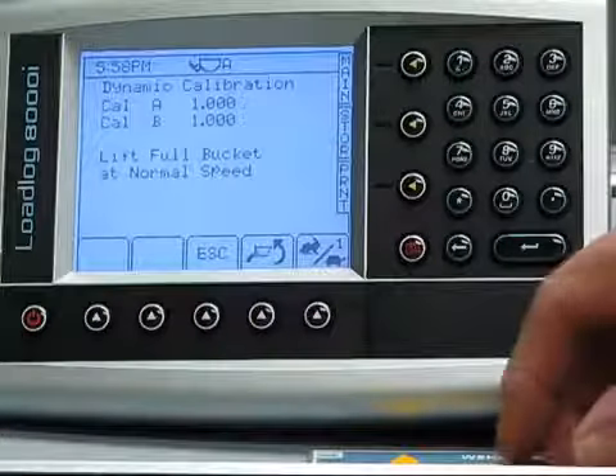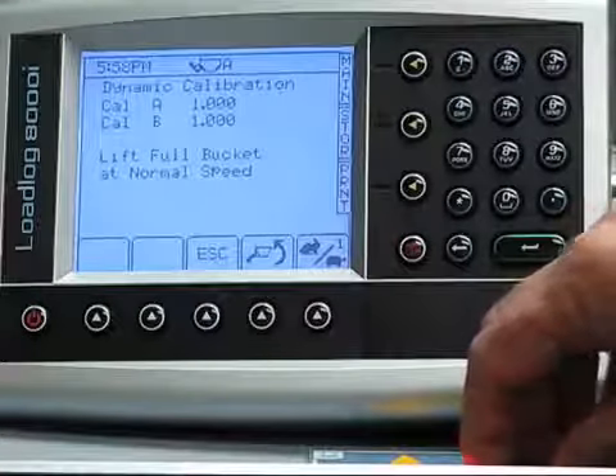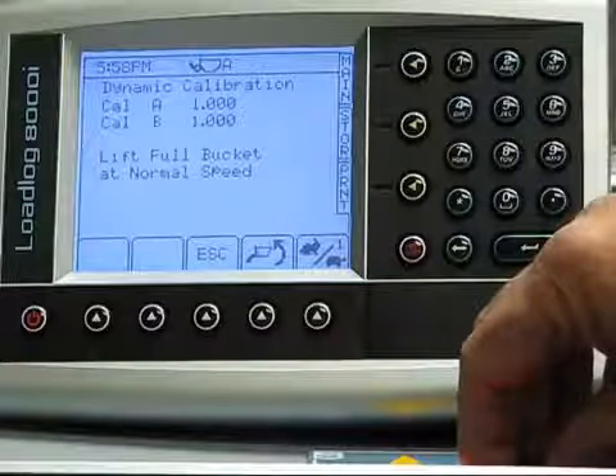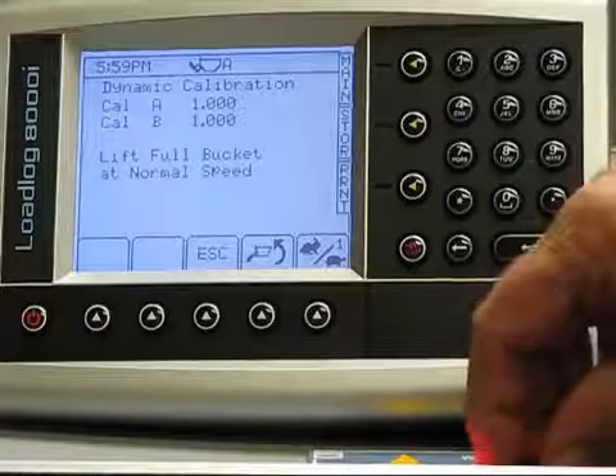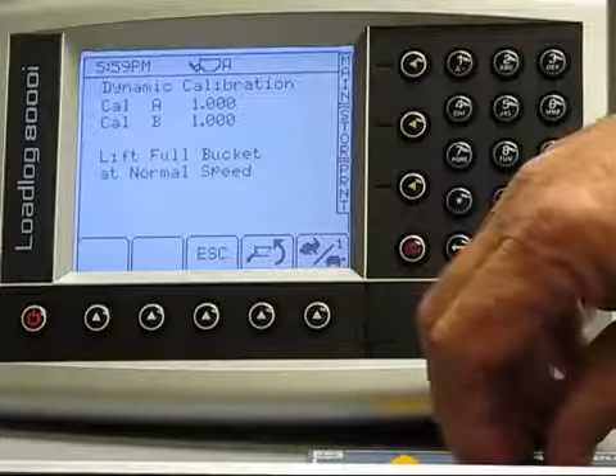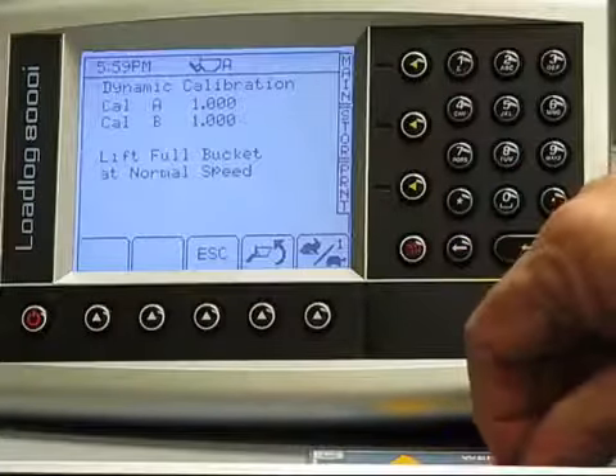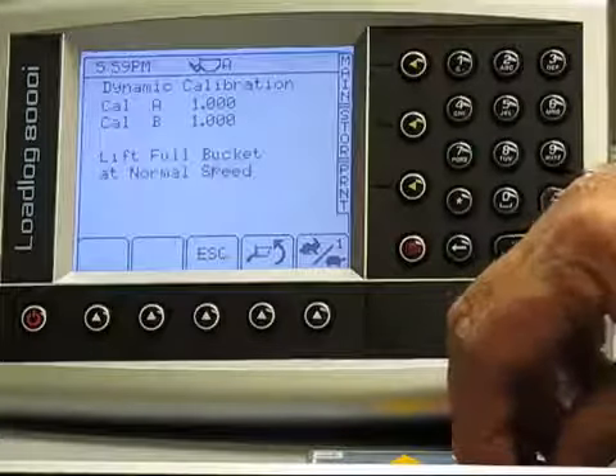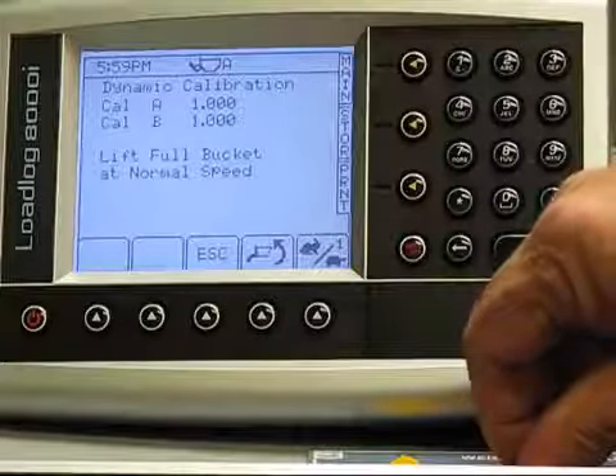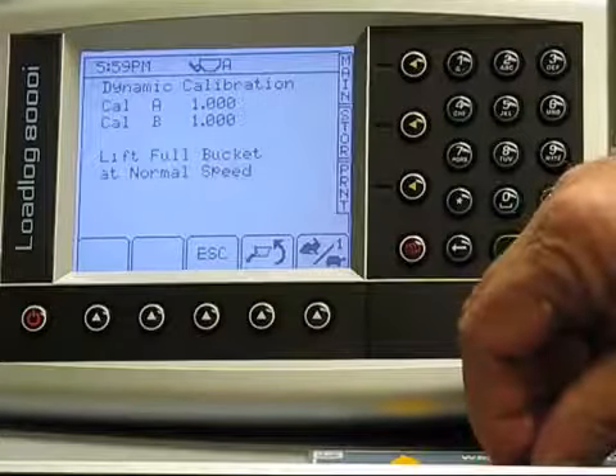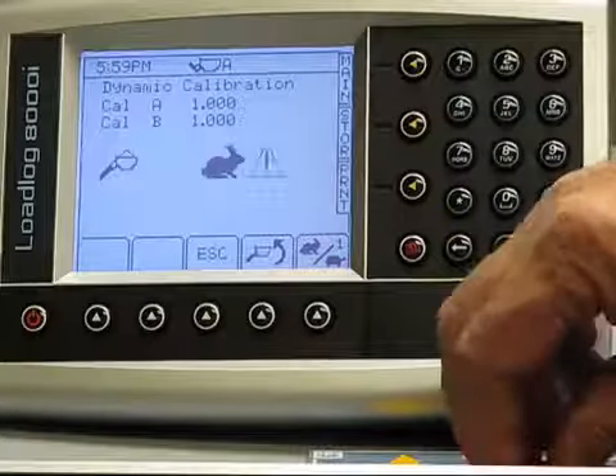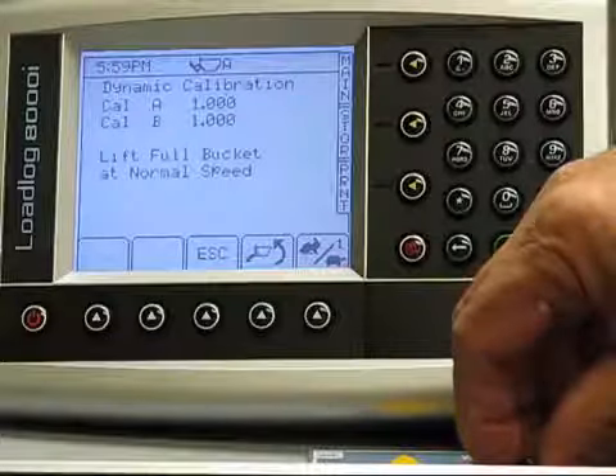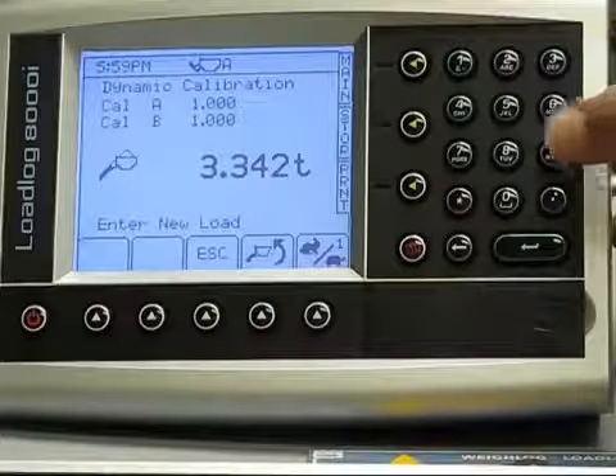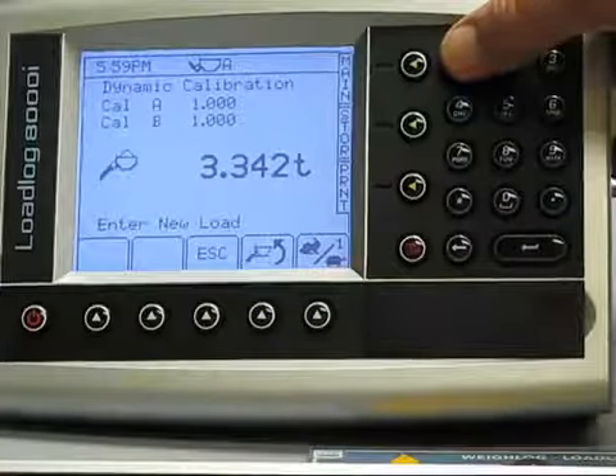We're going to fill this bucket all the way full, and because we don't have a standard weight right this moment, we're going to call this a 10-ton load. So we just lift the bucket with the load in there. Again, too fast. We'll get there.